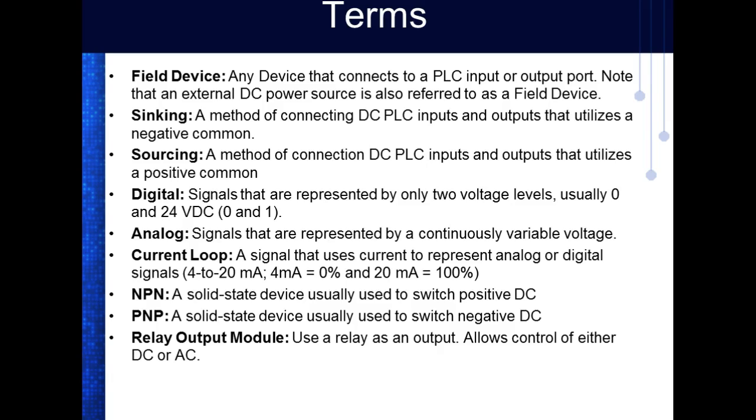I'm sure there's a, now these 4 to 20 milliamp current loops, we used to teach how they did this. And basically what's nice about the 4 to 20 milliamp current loop is that the way these devices work, as long as you don't exceed the range of what's capable on your inputs and your outputs, this is immune to the length of the wire. So that means you could run these things 1,000 foot or you can run them 100 foot. And what the driver does is puts out enough voltage to give you 4 milliamps for a 0 and 20 milliamps for a 1.